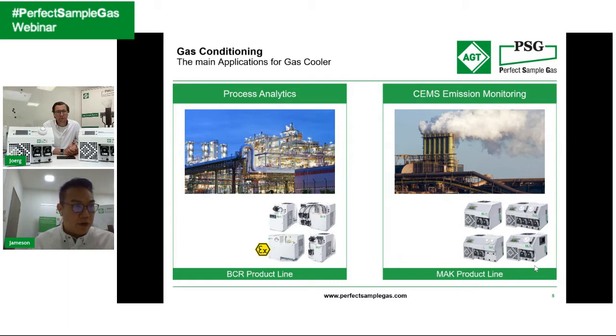They are positive pressure. Now on the emission side, we have to reconsider that truly we need a sample pump on the downstream. We have to extract the sample, to siphon the sample, because the stack is slightly below ambient. It is like negative. So therefore, we always need a pump.